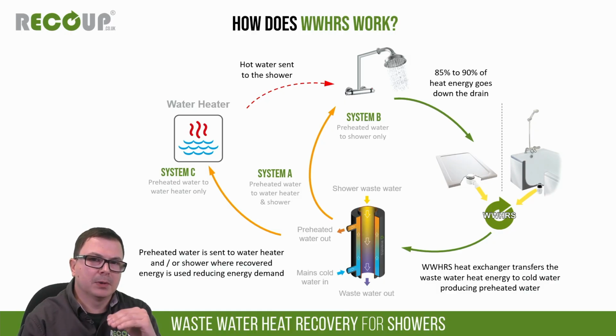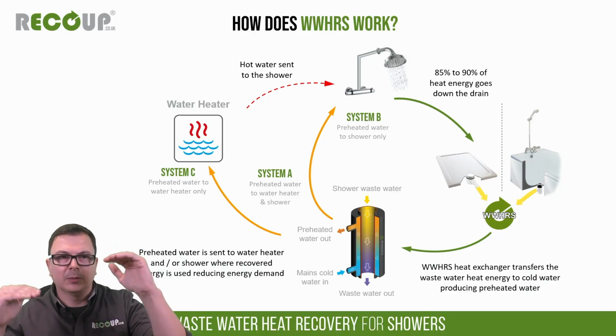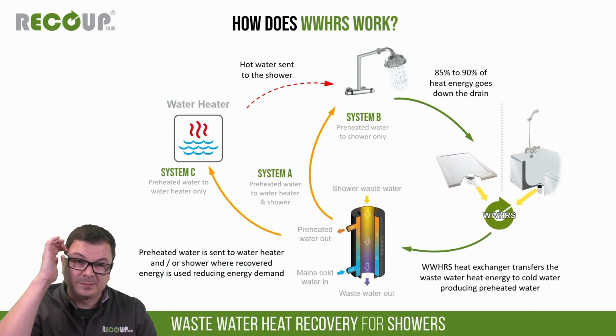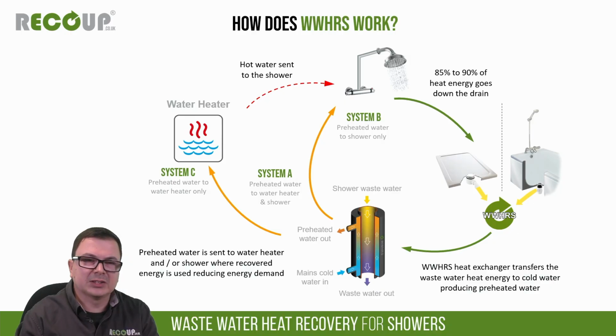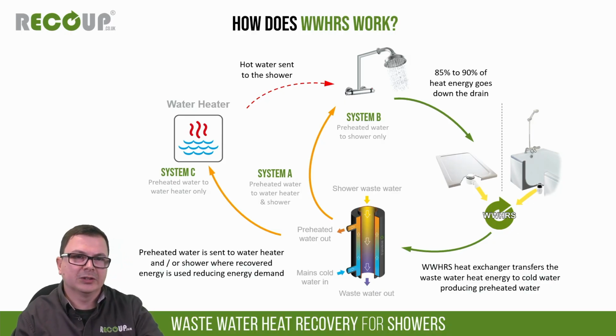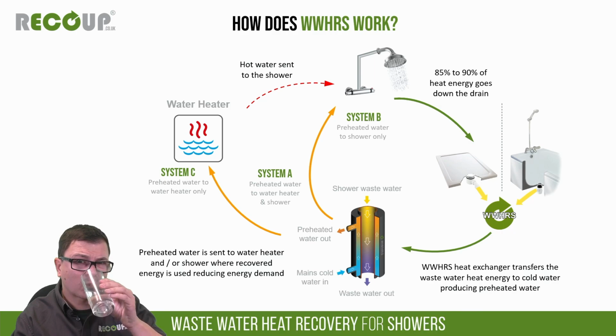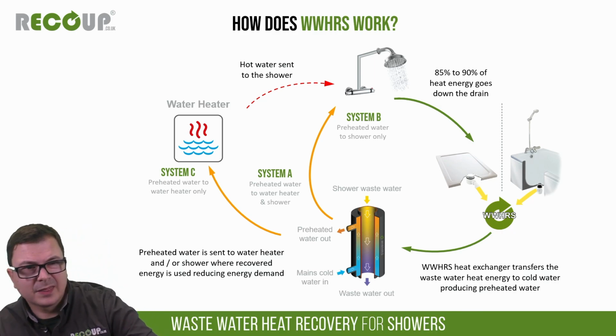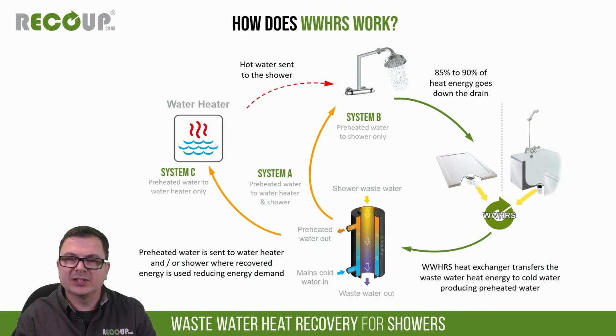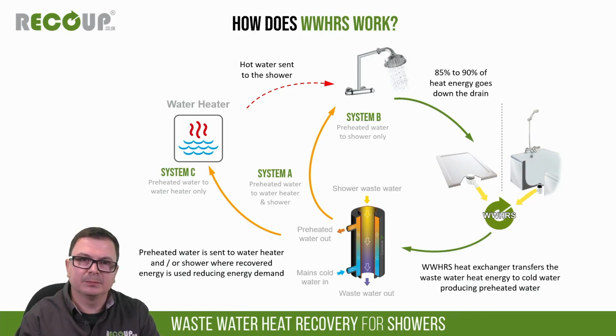Now we use most of our preheated feed at around 25 degrees, just topping it up with water from the water heater, almost flipping the ratio the other way. So with that scenario, we're using less domestic hot water at the shower itself. This is the lesser efficiency system, but the pipework and ease of installation are really advantageous.